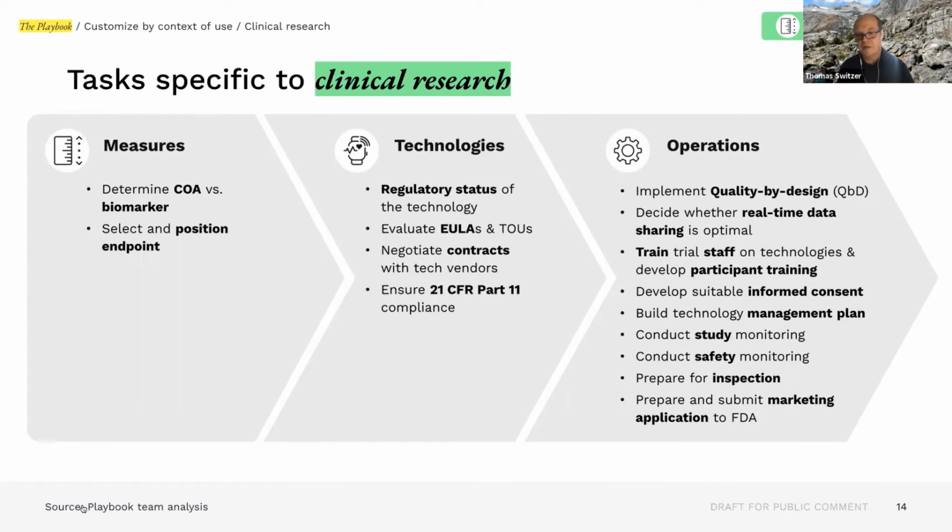And I think again, it's something that's the expectation, and we kind of need to design around that fact. Looking at your management plan, again, this is device provisioning. What do you do at the end of the study? Do you need to recalibrate some of these tools? They're calibrated before they go out, and you need to bring back a subset and then have them recalibrated to see if there's been any signal drift so that you can still say that your signal is accurate.